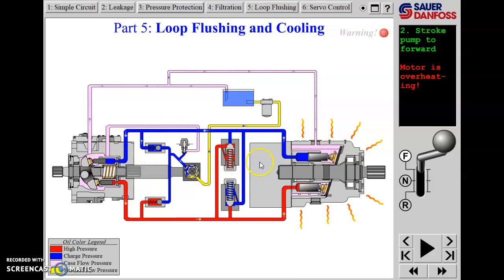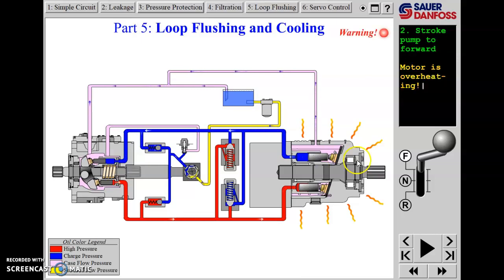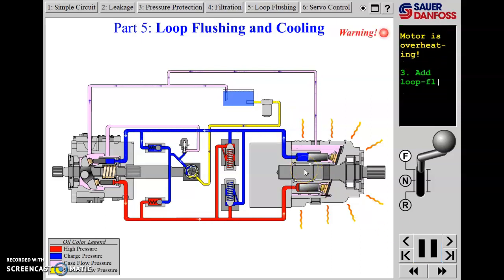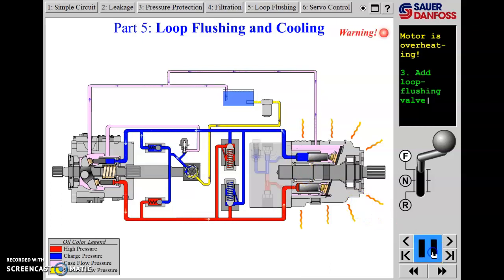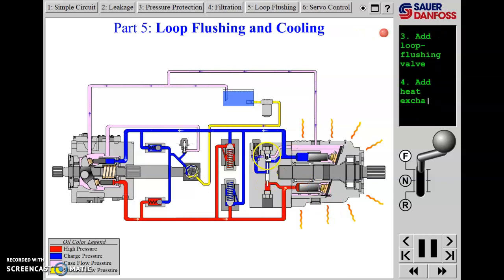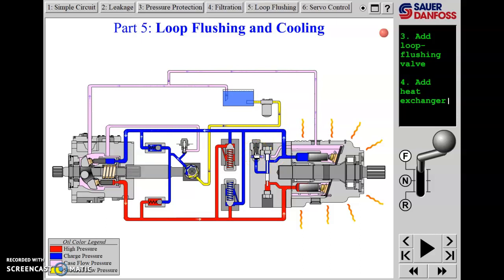The oil can get very, very hot very quickly. The motor, the pump, and all hydraulic components are heating up, and we can melt O-ring seals and cause damage to metal components as well. So what they're going to suggest is putting in a loop flushing system, which consists of a loop flushing valve — with two parts: a flushing shuttle valve and a flushing relief, sometimes called an operating charge relief.